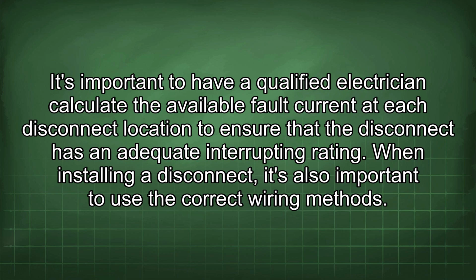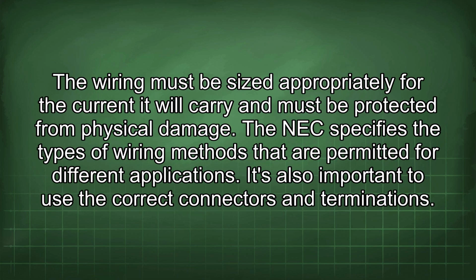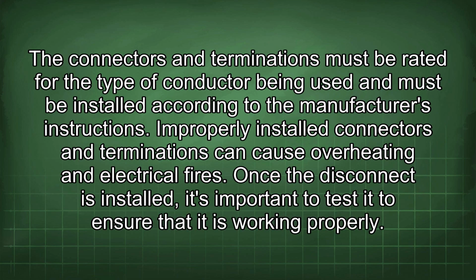When installing a disconnect, it's also important to use the correct wiring methods. The wiring must be sized appropriately for the current it will carry and must be protected from physical damage. The NEC specifies the types of wiring methods that are permitted for different applications. It's also important to use the correct connectors and terminations. The connectors and terminations must be rated for the type of conductor being used and must be installed according to the manufacturer's instructions. Improperly installed connectors and terminations can cause overheating and electrical fires.